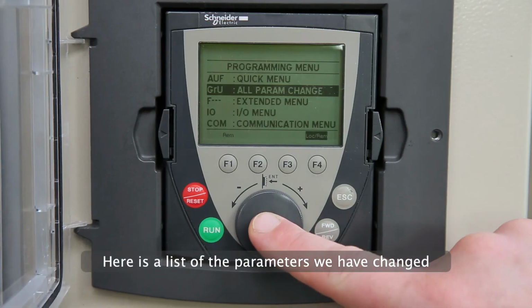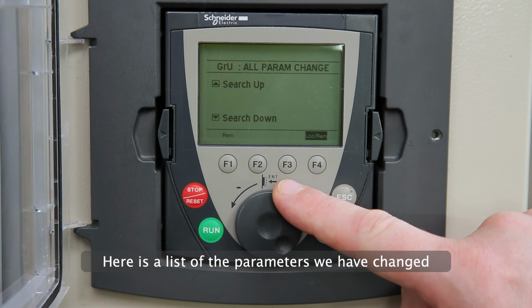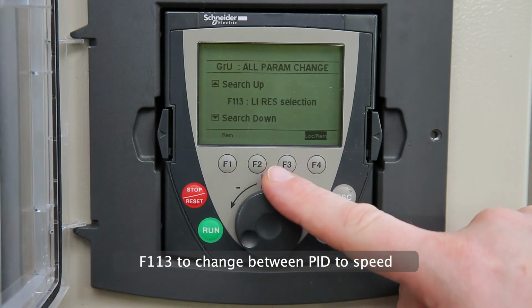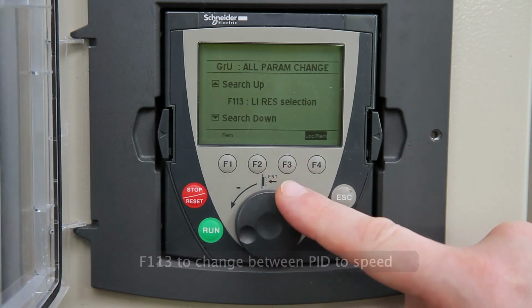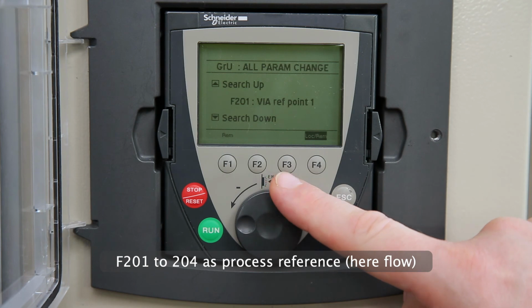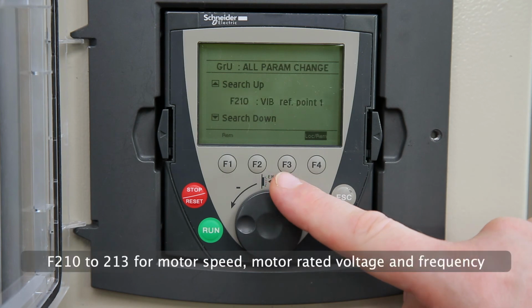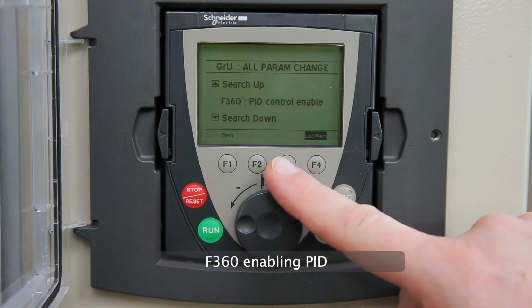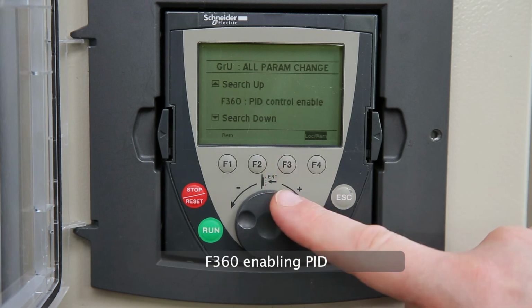Here is a list of the parameters we have changed. F113 to change between PID to speed, F201 to F204 as process reference, here flow, F210 to F213 for motor speed, motor rated voltage and frequency, F360 enabling PID.